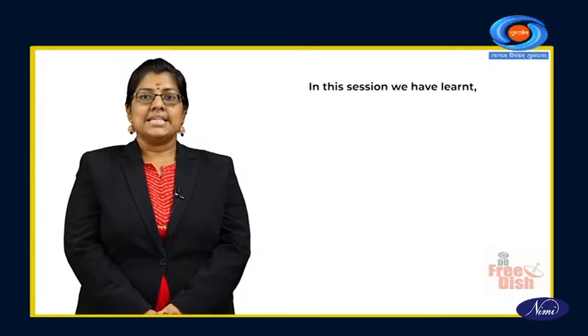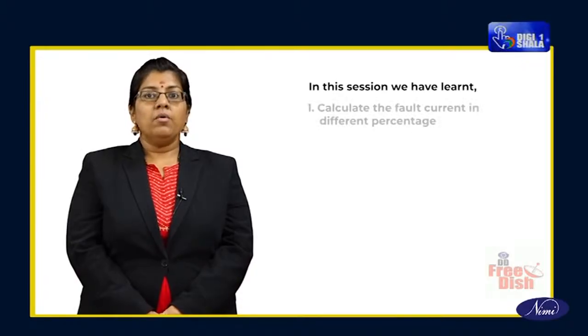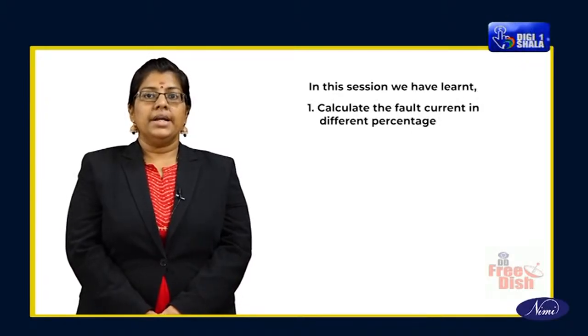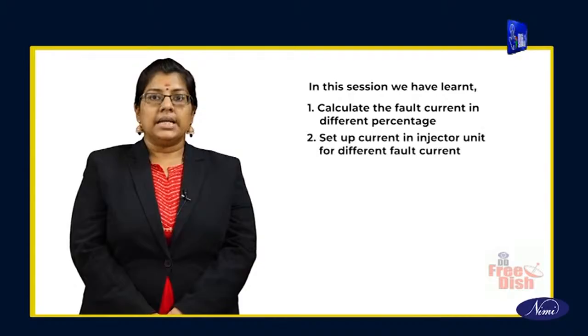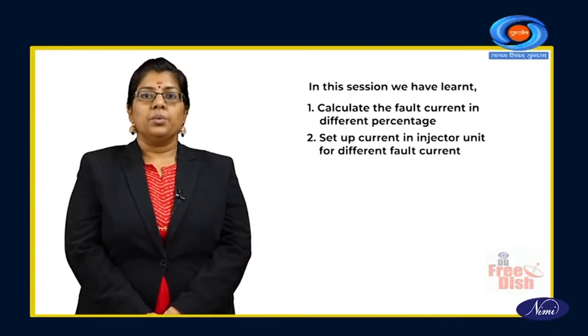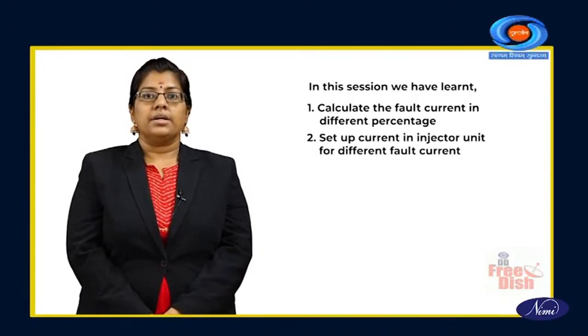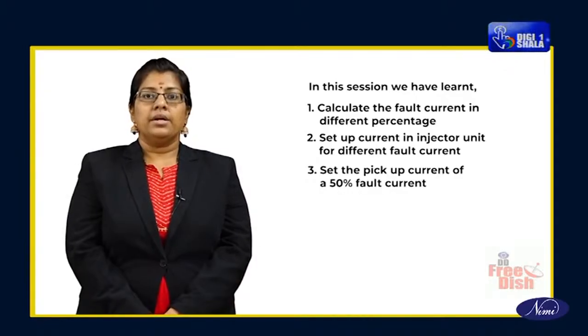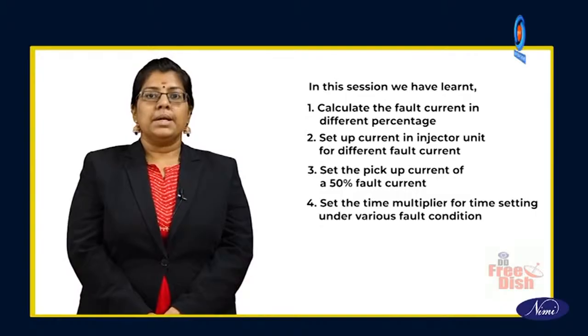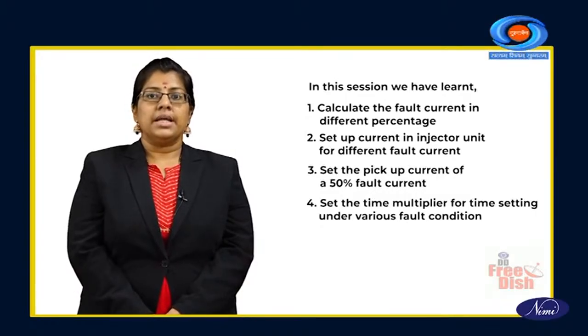Recap. In this session, we have learned how to calculate the fault current in different percentages, set up current in the injector unit for different fault currents, set the pickup current of a 50% fault current, and set the time multiplier for time setting under various fault conditions.